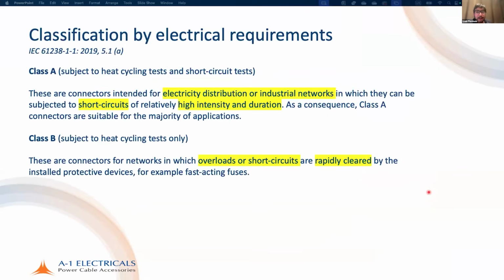Lugs or connectors, which are mechanical compression connectors, are classified by two requirements. Class A are connectors that are subject to heat cycling tests as well as short circuit tests. So these are connectors intended for electricity distribution or industrial networks, in which case they can be subject to short circuits of relatively high impedance, a high intensity and duration. As a consequence, Class A connectors are suitable for the majority of applications. So this is what is used where there's a high short circuit intensity and duration, and the connector has to be able to withstand this. Very important subject.